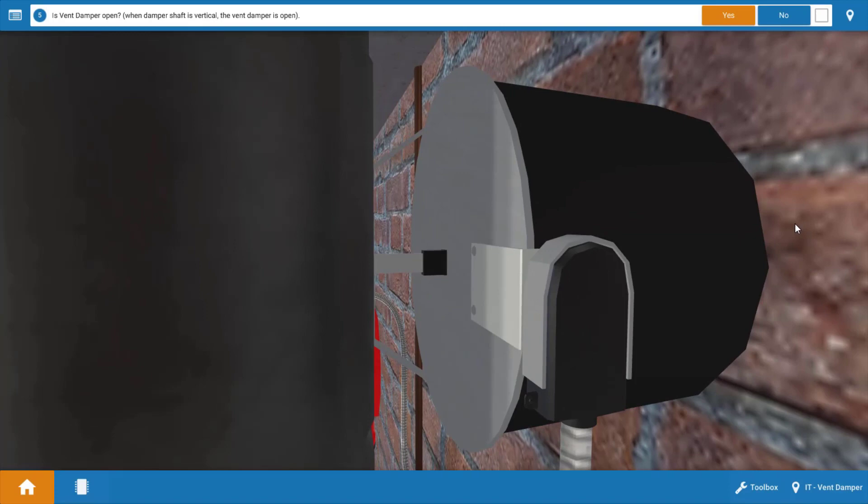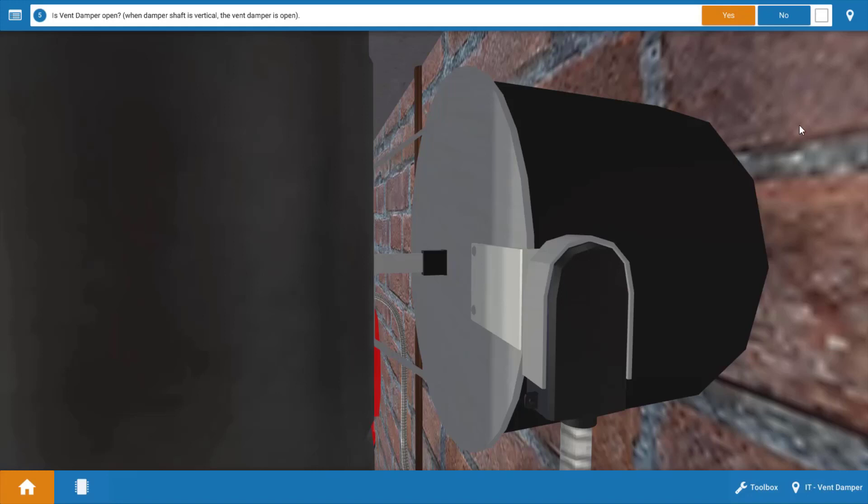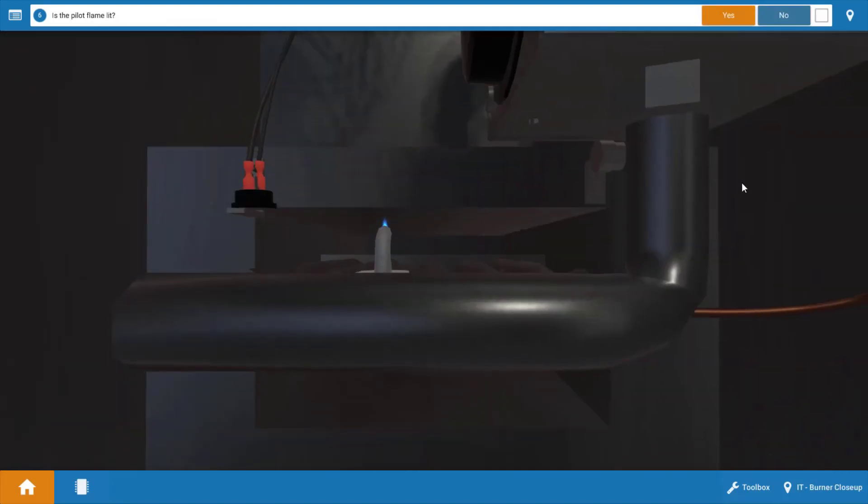Next, we want to verify that the vent damper opened. Now, the vent damper is just going to close off the flue passage on each off cycle to prevent heated air from escaping up the draft diverter or draft hood. If you look at the shaft of the vent damper, it's vertical, which indicates that the damper is in fact open. Now if it's closed, the shaft is going to be flat or horizontal. So yes, our vent damper is open.